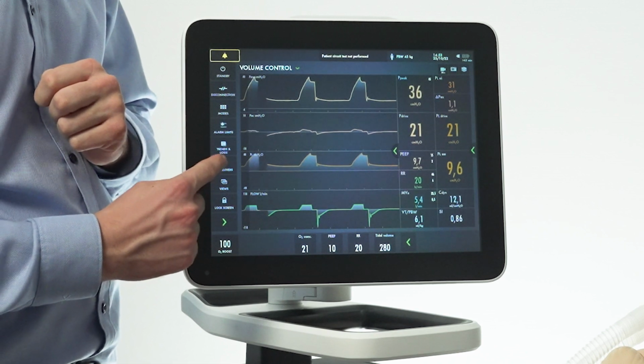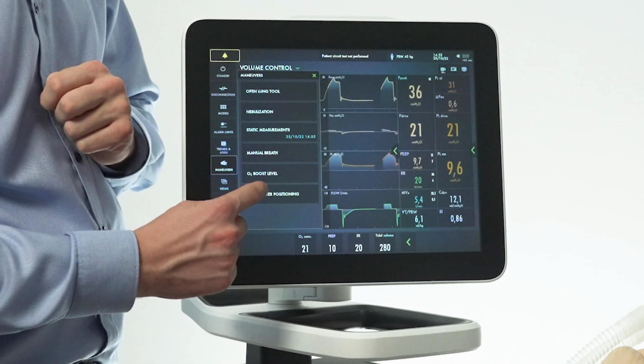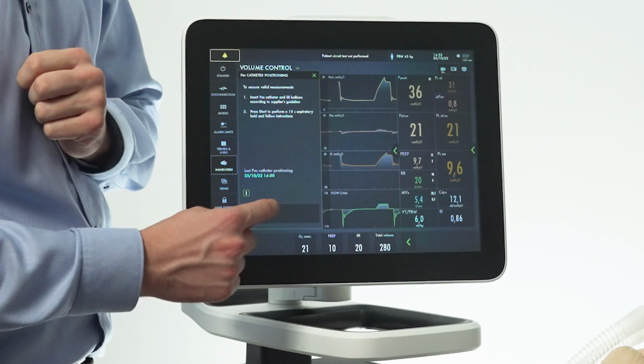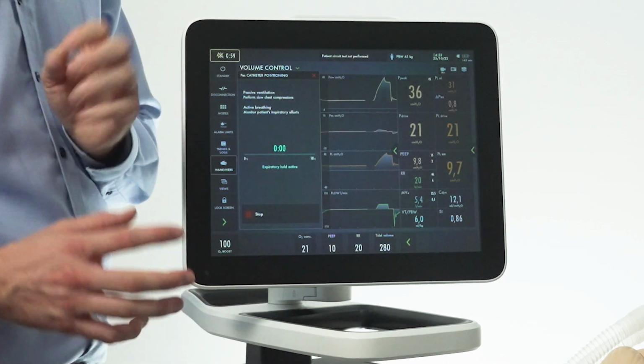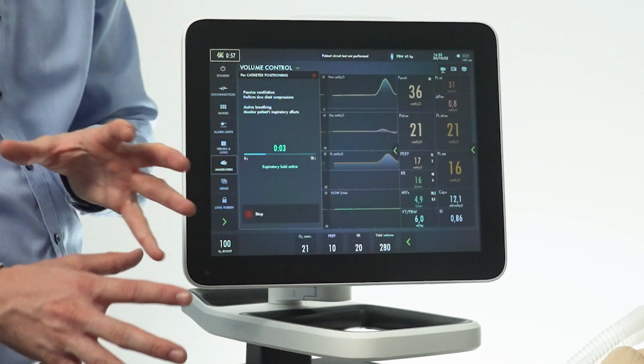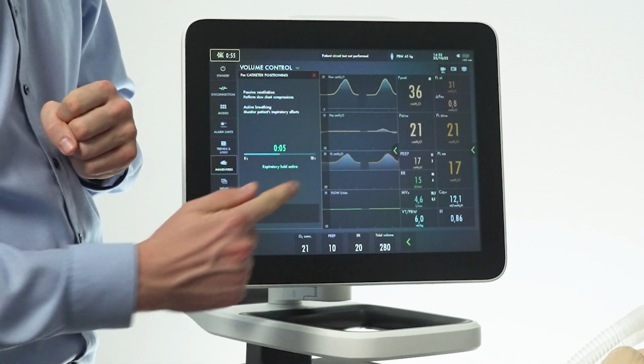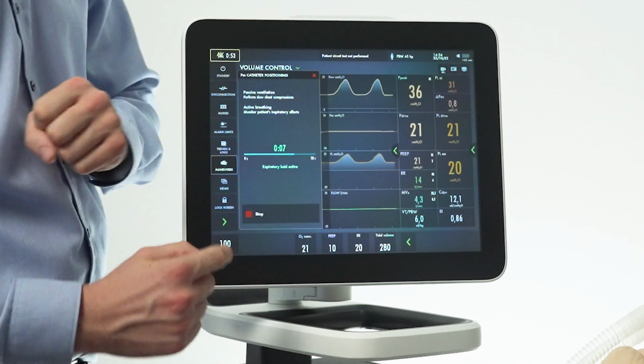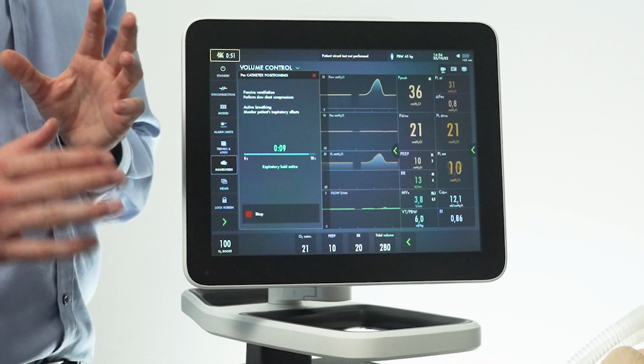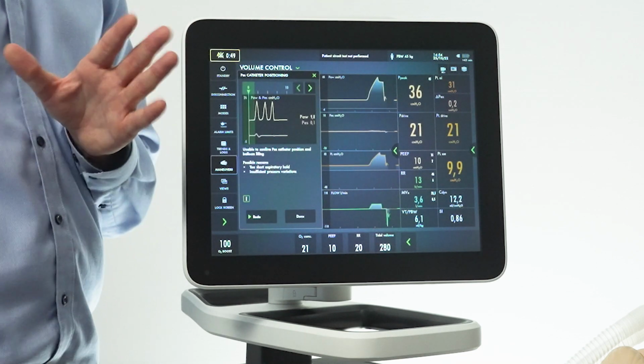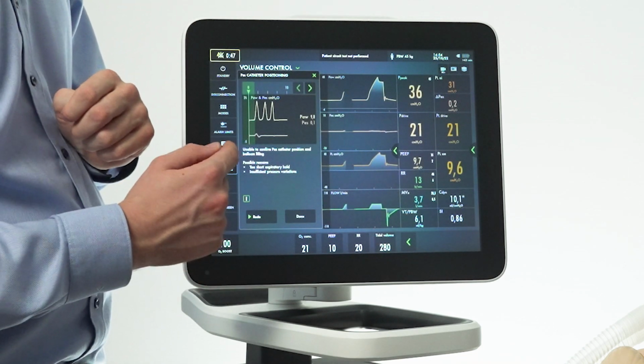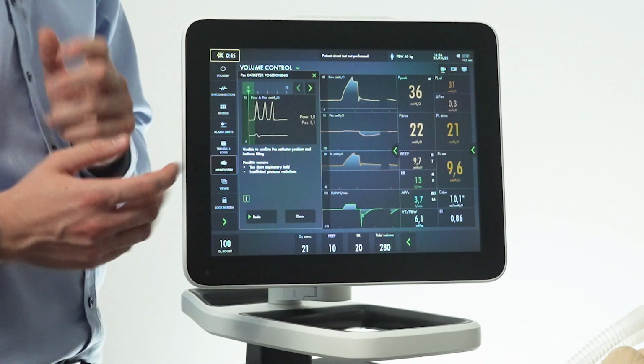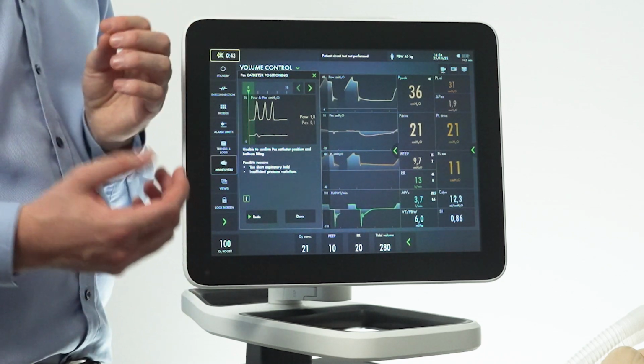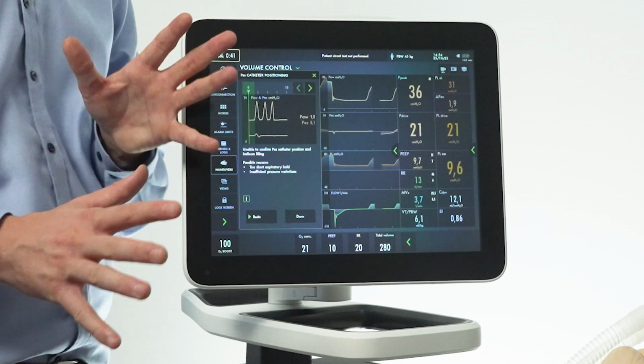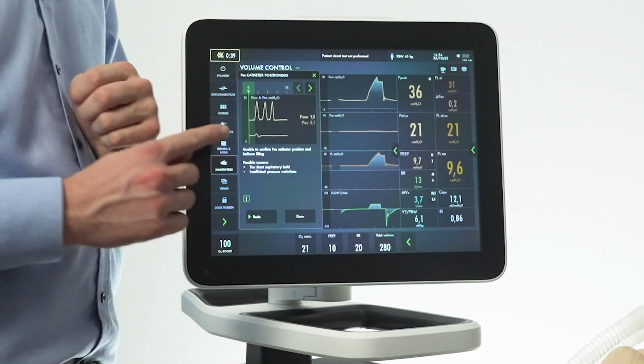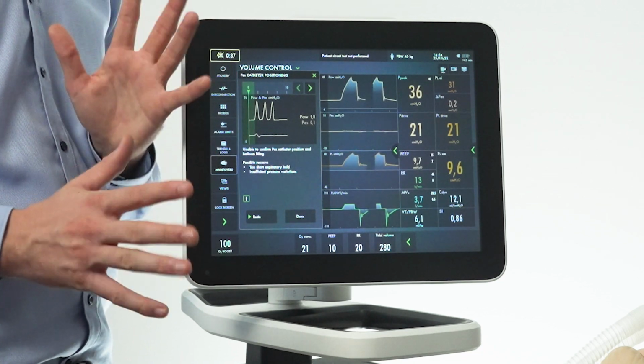So once again, we go to maneuvers, Pes catheter positioning, we press start, and we have someone compress the thorax of our patient. What we can see now clearly is that airway pressure is rising, but esophageal pressure is rising to a much lesser extent. And as you can see, the ventilator now tells us that it's unable to confirm the positioning because esophageal pressure barely changed. When this happens, there are a few problems you need to consider.